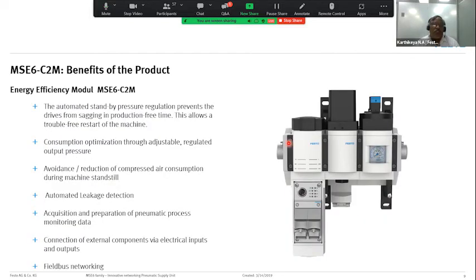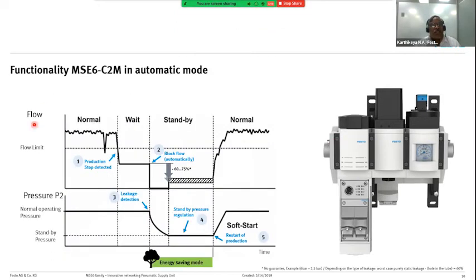It depends upon the functionality of the process, whether you need complete shutdown or you have to handle a standby pressure. Based on that, you have to select the modules. Here you can see in normal operation you have the normal flow. And when the machine is on standby, we can predefine the time for which it continuously monitors, and after that it completely closes off. It shuts down, and we can also define a standby pressure to be given to the process.